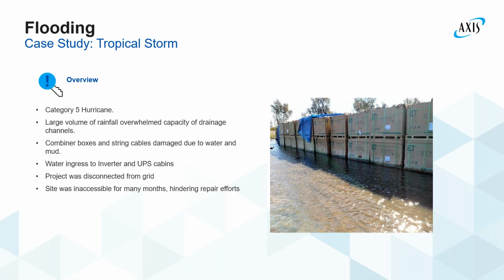Large volume of rainfall overwhelmed the drainage channels. The site in the tropics was under construction at the time, and you can see a lot of shipping containers waiting to be opened up and deployed on site. All those containers contained inverters, and as you can see, the river burst and the water came through and went into those containers. So of the combiner boxes and string cables that were installed, they all got flooded with mud and water, so they all had to be replaced.